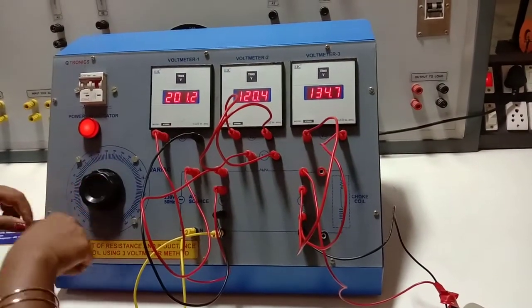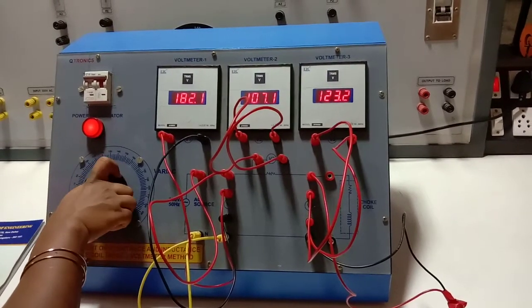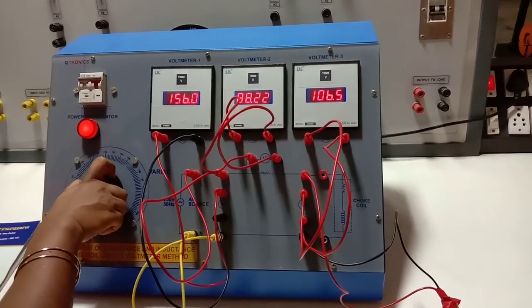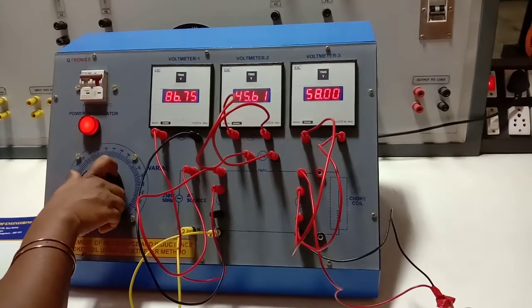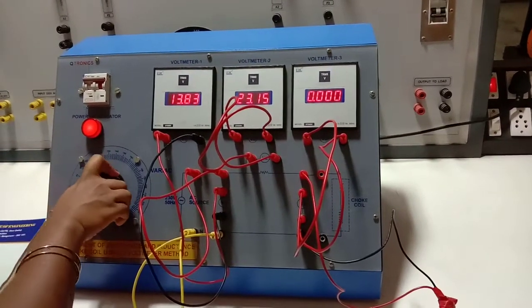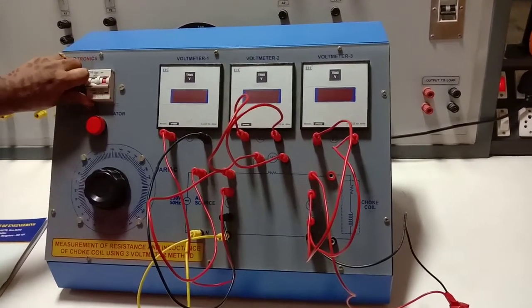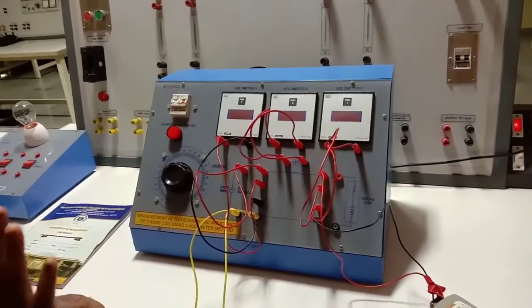Once you have done this, then you have to go back or bring back this variac to 0 position. Bring back this variac to 0 position slowly. Once it come back to 0, next switch off the MCB, then switch off the main supply. After that only you have to remove the connection.